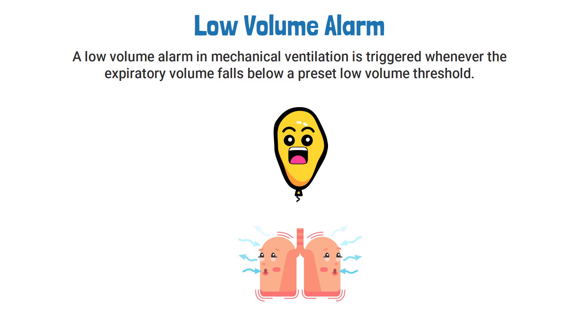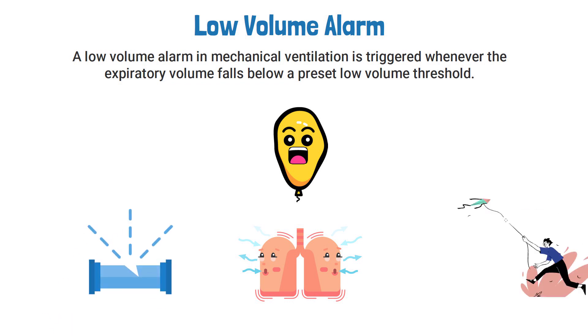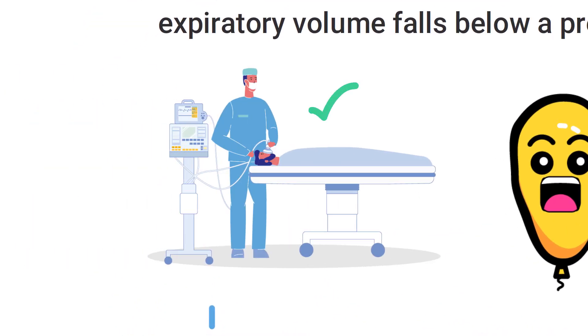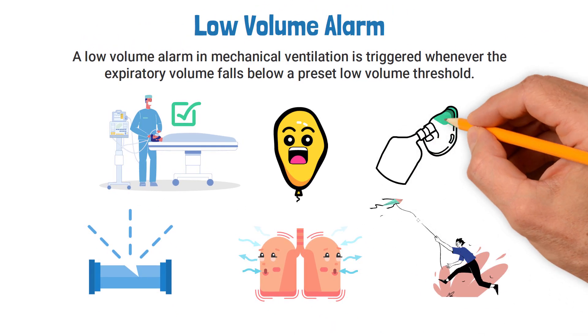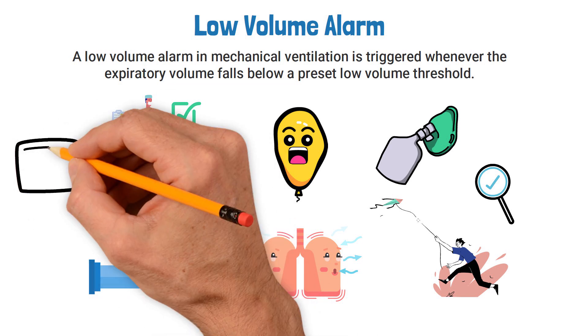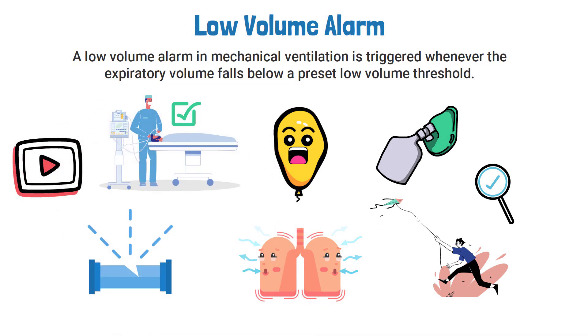Similar to the low pressure alarm, this alarm will also sound whenever there is a leak or disconnection in the system. When this is the case, the respiratory therapist must ensure that the patient is being ventilated and provide manual breaths if necessary until the source of the issue is identified and corrected.